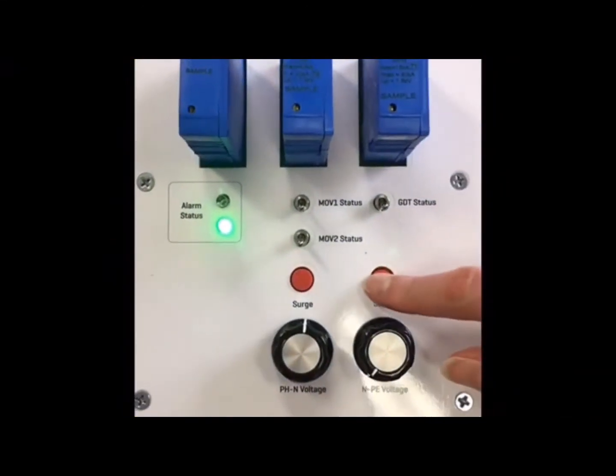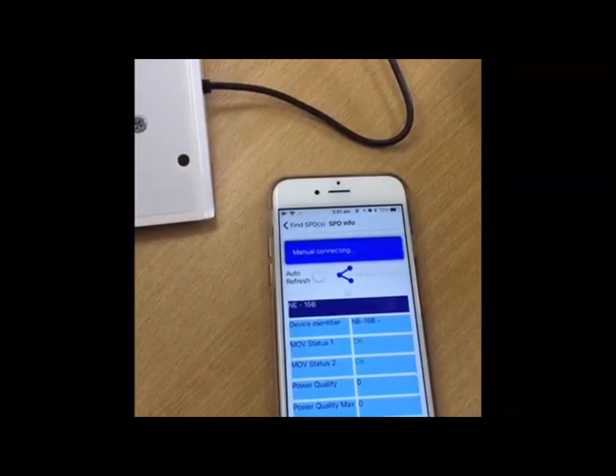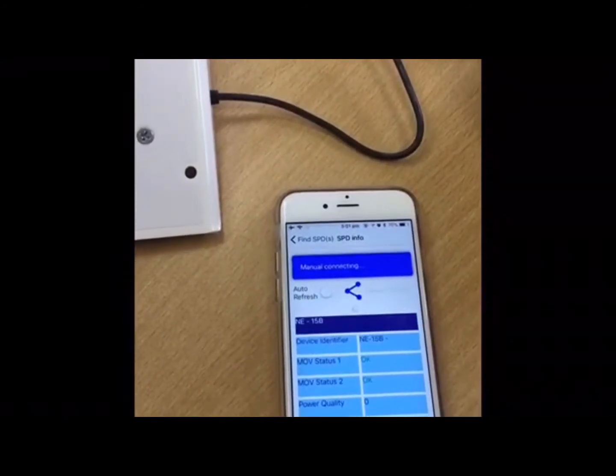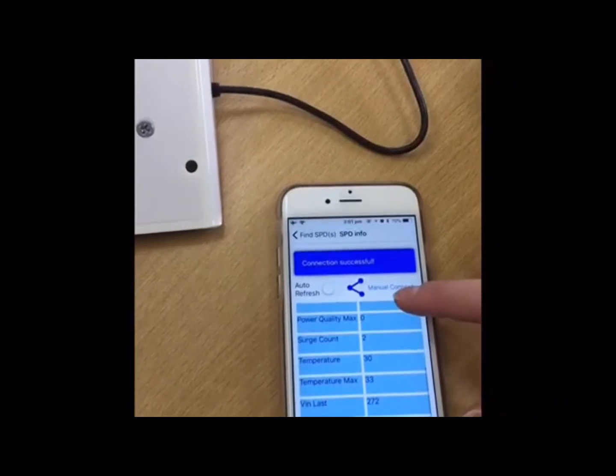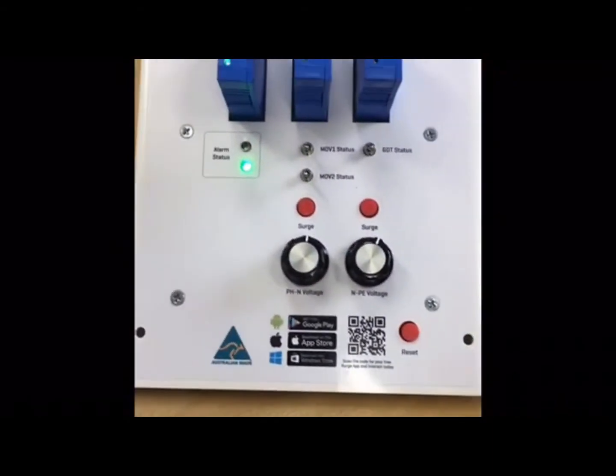The NE15B modules use a single gas discharge tube or GDT as part of its protection circuit. To simulate an internal fault, toggle the GDT switch to the up position and observe both MOV status tabs in the SPD app changed to fail.